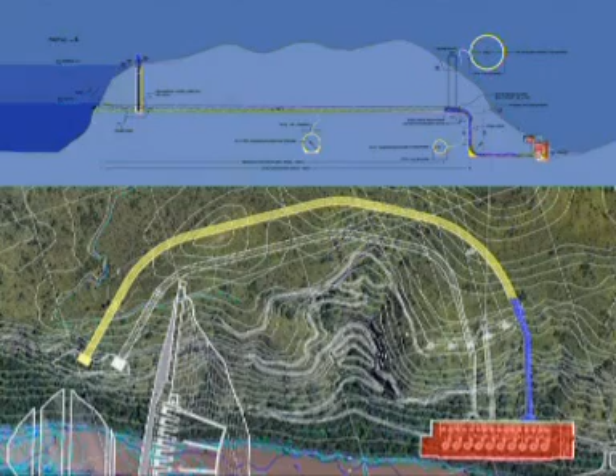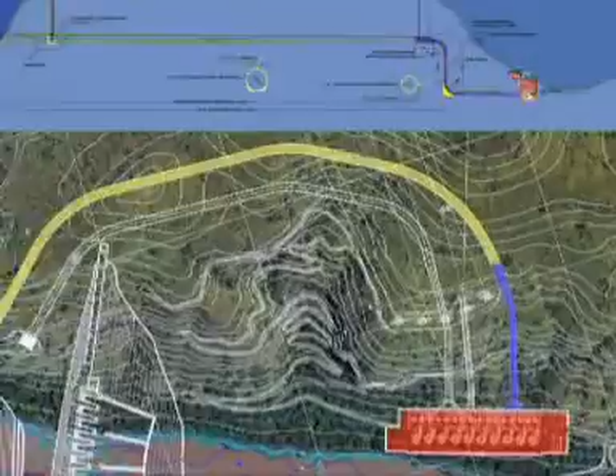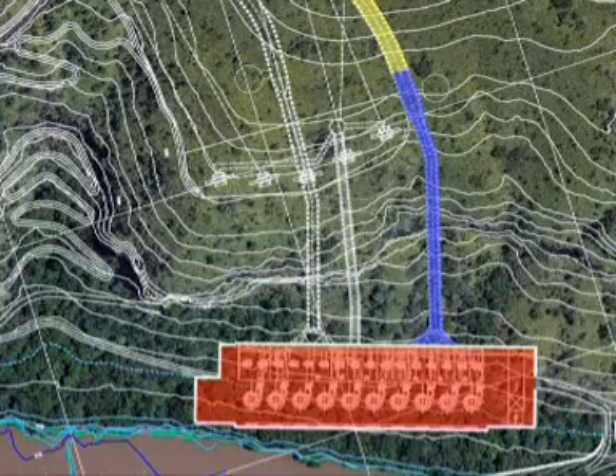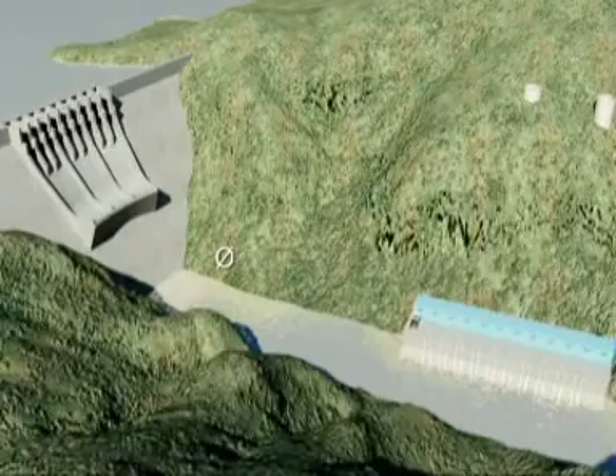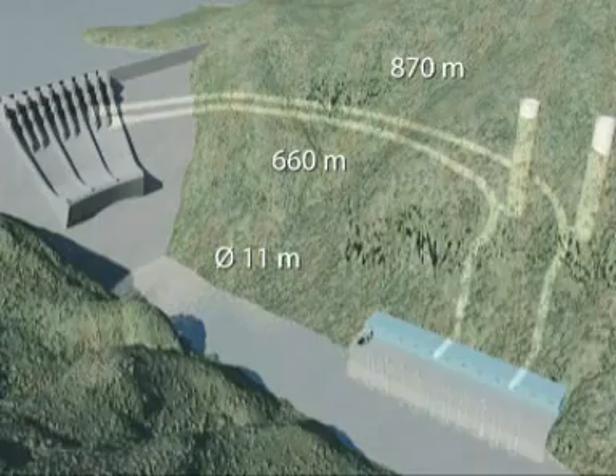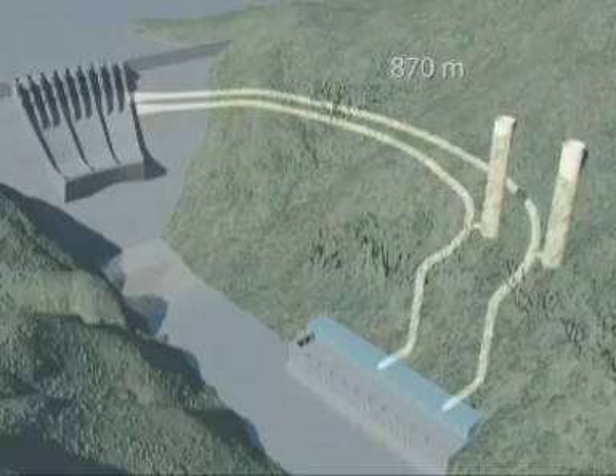Two separate intakes and power tunnels will be constructed, each serving 5 generating units via 2 steel-lined penstocks and manifolds. The intakes are equipped with roller gates raised and lowered by oil-operated servo motors and bulkhead gates lowered and raised by hoist. The 2 power tunnels, 11 meters in diameter and concrete-lined, will be 660 meters and 870 meters long.